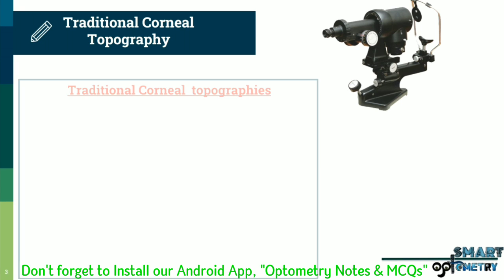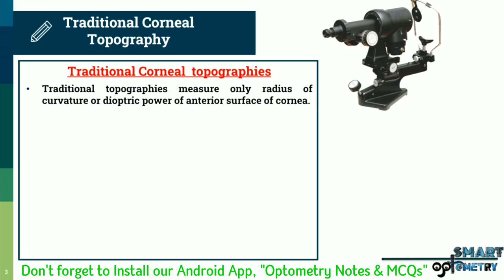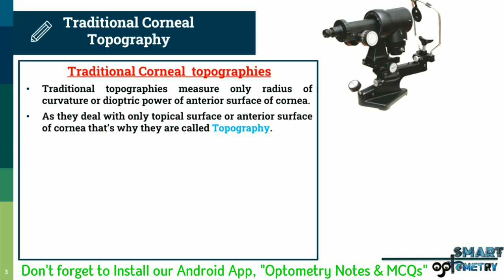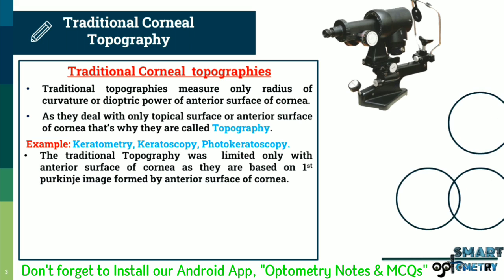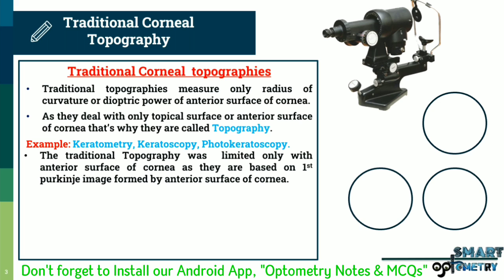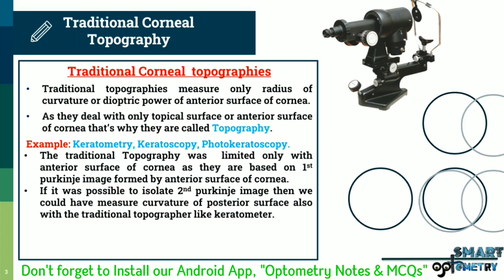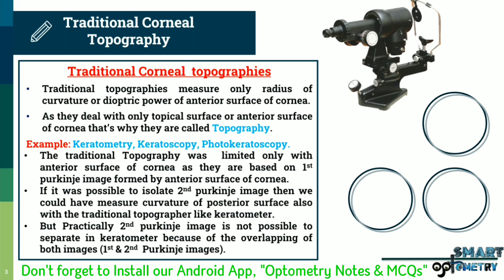Traditional topographies measure only the radius of curvature or dioptric power of the anterior surface of the cornea. As they deal with only the topical or anterior surface of the cornea, they are called topography — for example, keratometry, keratoscopy, and photokeratoscopy. Traditional topography was limited to the anterior surface because it is based on the first Purkinje image formed by the anterior surface. If it were possible to isolate the second Purkinje image, we could measure the curvature of the posterior surface as well. Practically, the second Purkinje image cannot be separated in the keratometer because of the overlapping of both mires, and the second Purkinje image is much dimmer compared to the first.